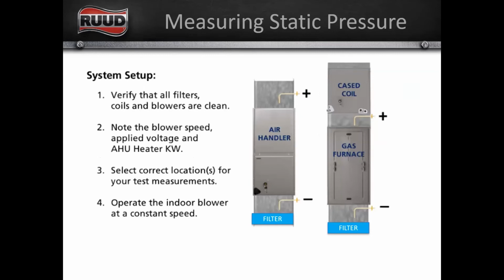The first thing that you need to do when you're checking static is make sure that everything's clean, right? You want to make sure that it's got a nice, good, clean new filter. You want to make sure that the blower wheel is good and clean, because those two things will affect your readings. Do not pull the filter out, check your static, and then put the filter back in, because now you have altered that number. When we check static, we want to check the static pressure between our indoor piece of equipment and the filter. If you pull the filter out, check static, and then put the filter back in, you have created a pressure drop by having that filter in the airflow that you have not accounted for, you haven't measured. So it always has to be between the filter and the air handler.